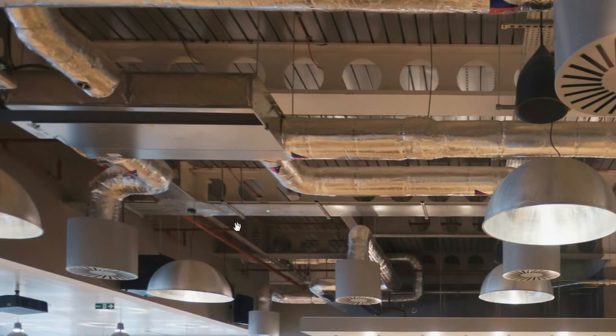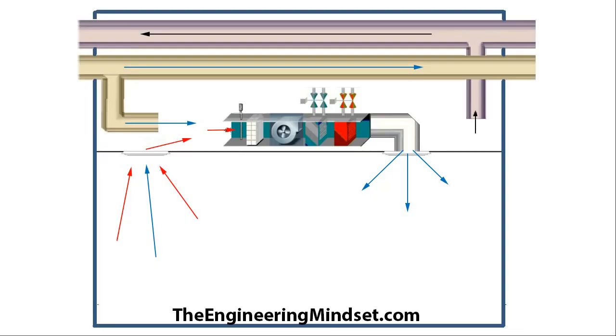If the false ceiling weren't there it would look something like this — the fan coil unit with ductwork supplying air through diffusers. The fan coil unit sucks up all the air in the space and pushes it across a heating and cooling coil, treating it to the right temperature. That air is then pushed out through ductwork and supplied through the diffusers.